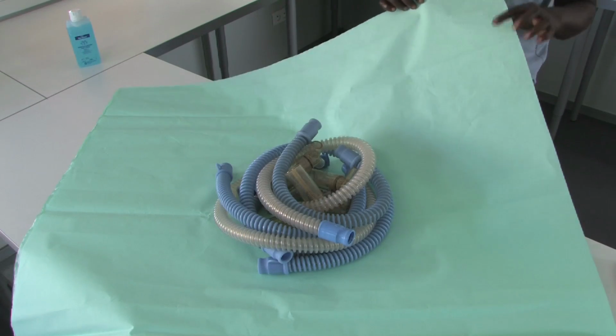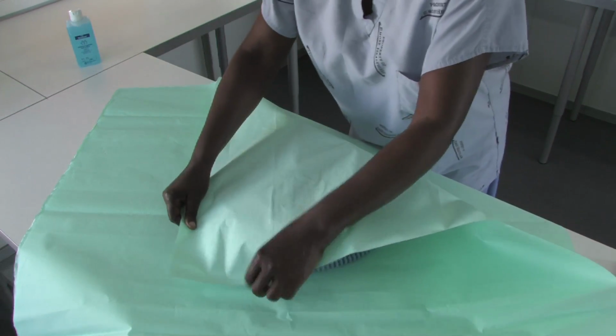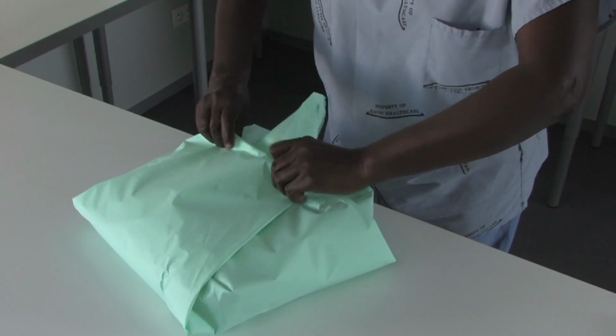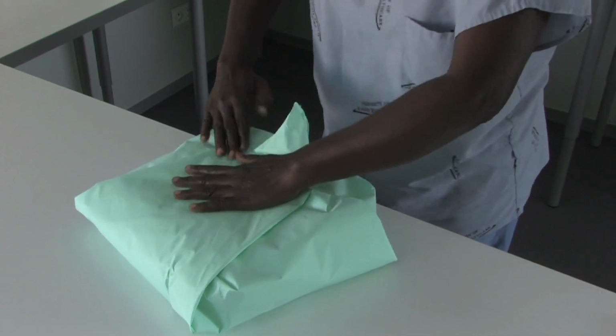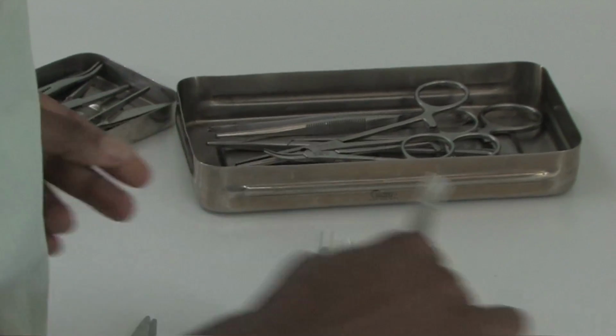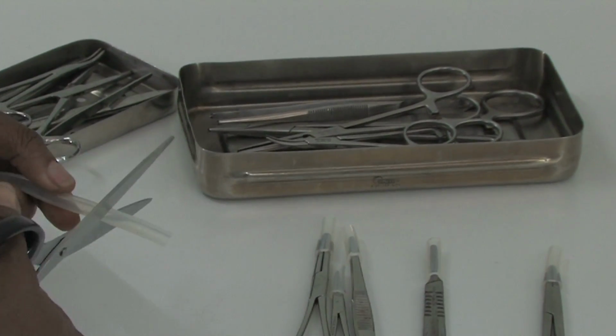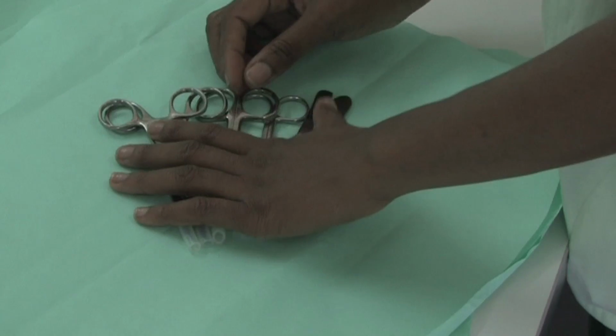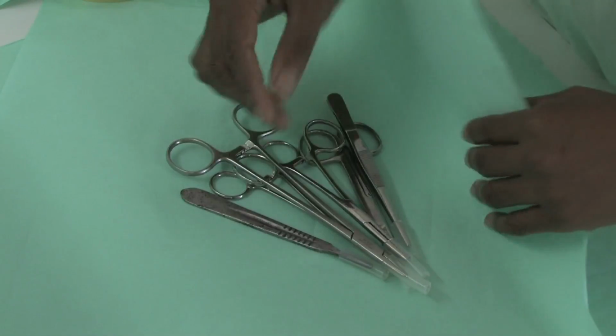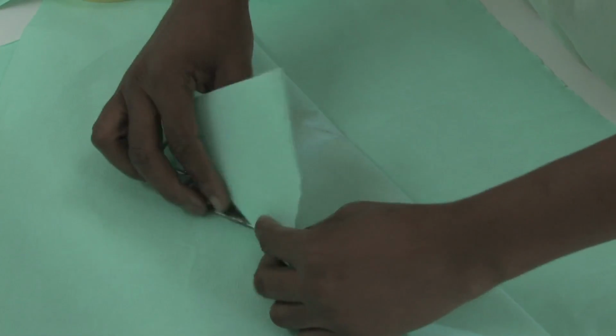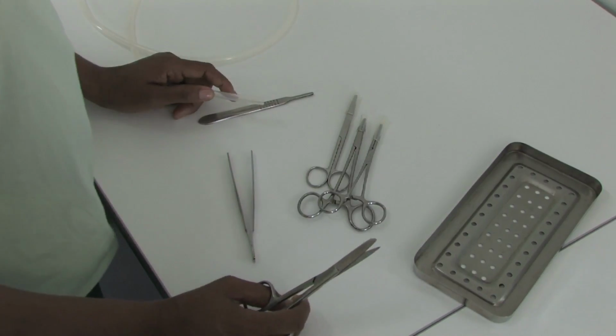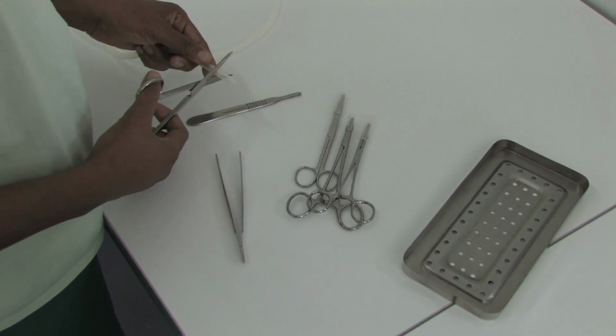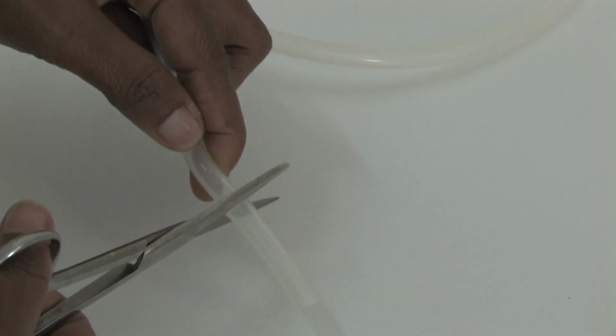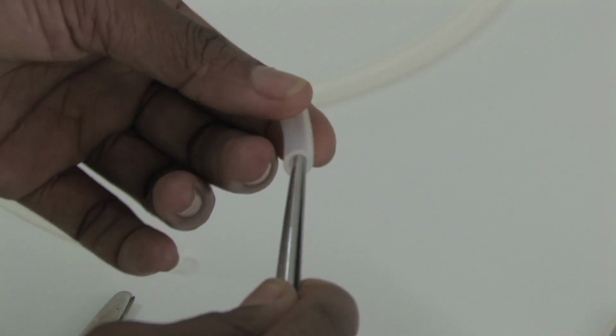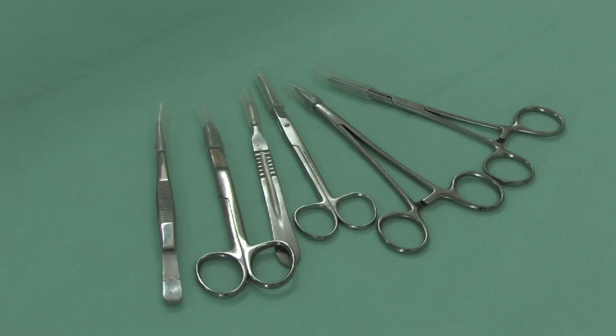Some devices, like anesthesia tubes and surgical light handles, can be wrapped directly in crepe sterilization paper. Similarly, it's recommended that dressing and suture sets, with only a few instruments, be wrapped directly in crepe sterilization paper to minimize the condensation and space taken up in the autoclave. In this case, the sharp ends must be covered with small pieces of silicone tubing to prevent them from piercing or tearing the paper during handling.